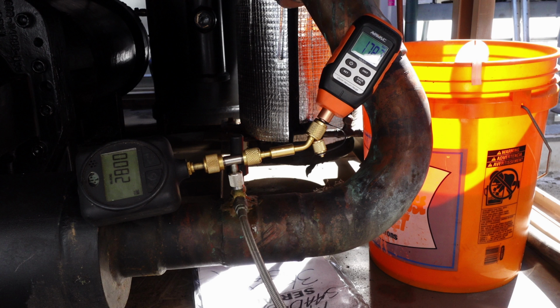Always mount your gauge in an upward orientation. Don't ever mount it downward. I've screwed myself many times because I did that without thinking. Especially on the discharge side of the system, oil will get down into the port of your gauge and then it's just screwed. So be careful with that.